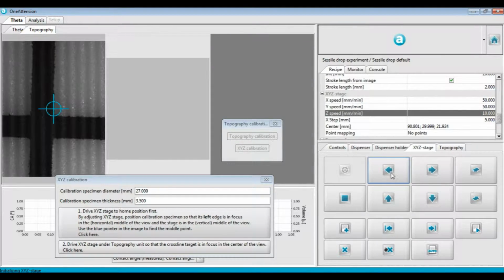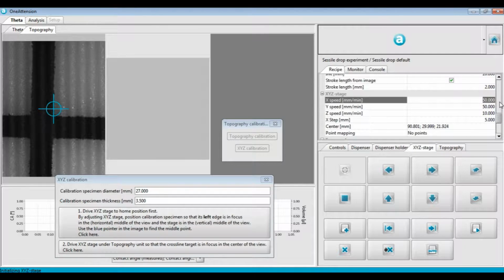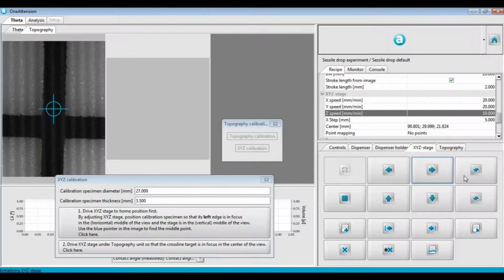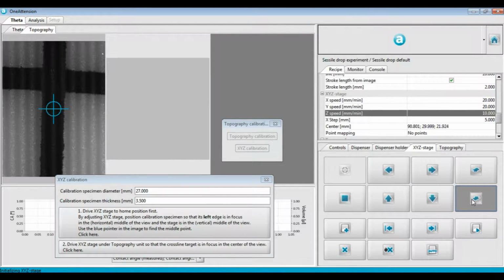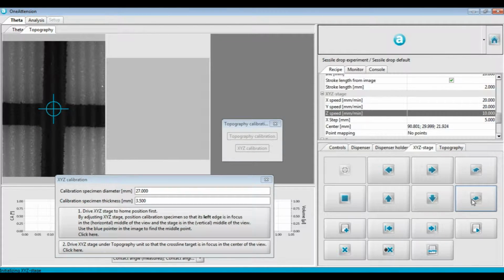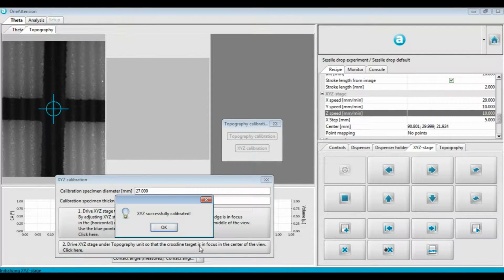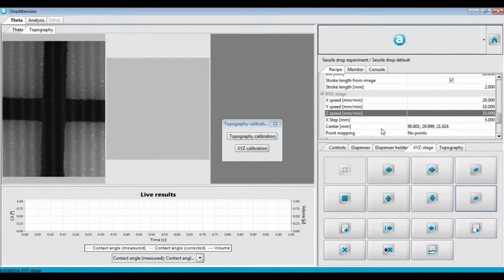This intersection is where the center of our sample is, and now we need to adjust those speed settings of our XYZ stage so that we can very finely position the center of our bullseye with the center of this cross. Once this alignment is complete, we can left-click the bottom box in the XYZ calibration window. And now we've completed the XYZ calibration.